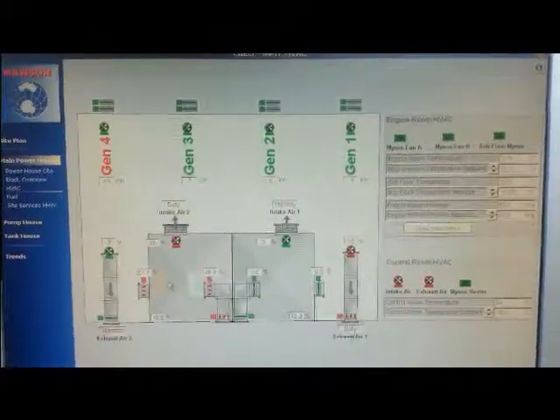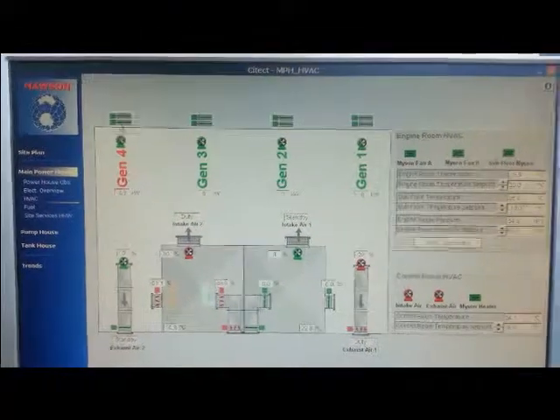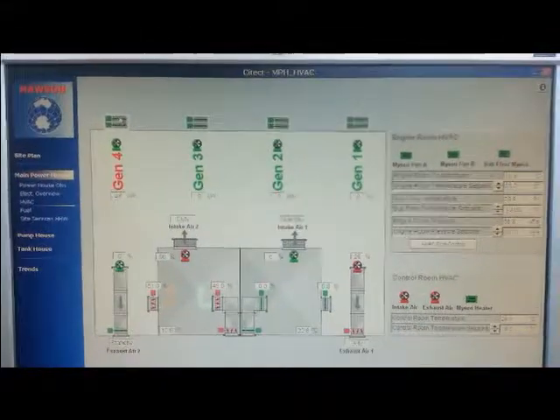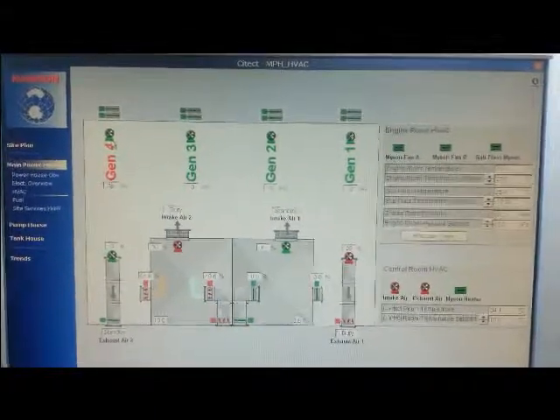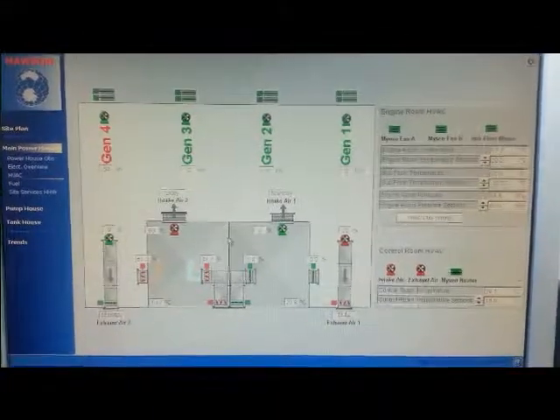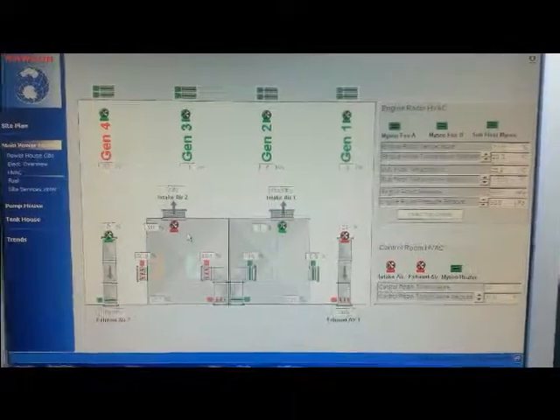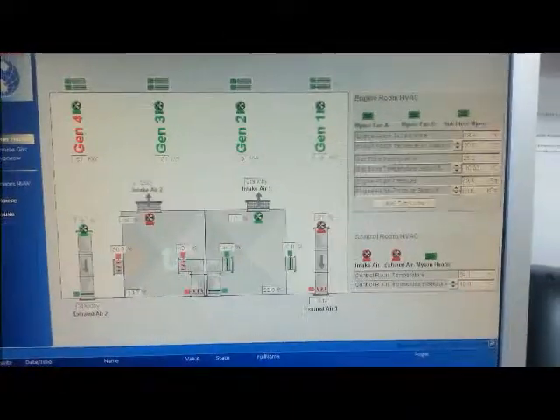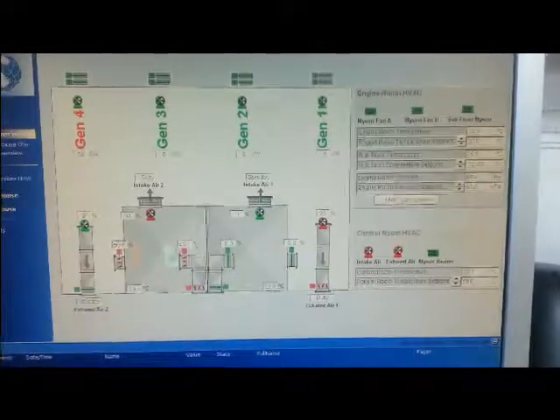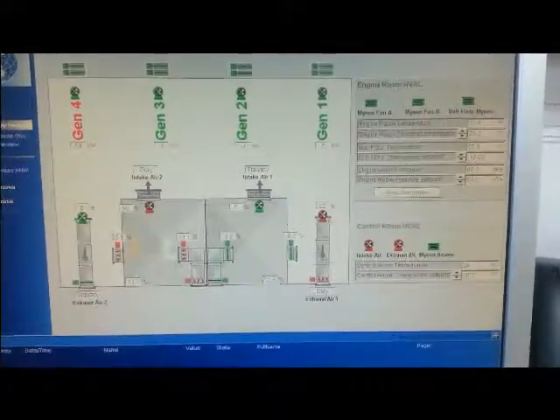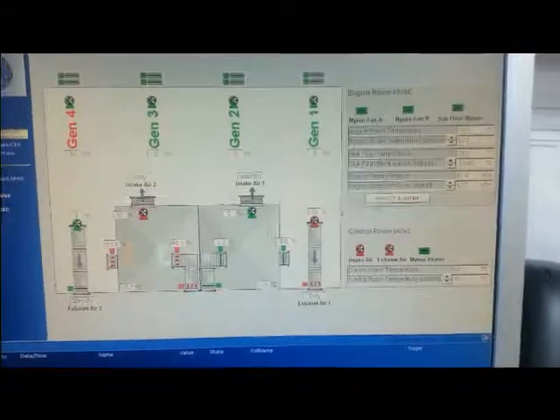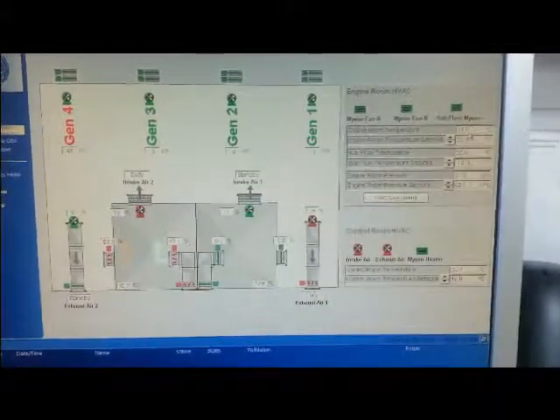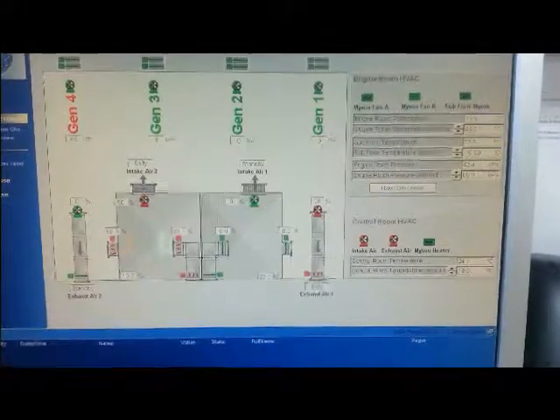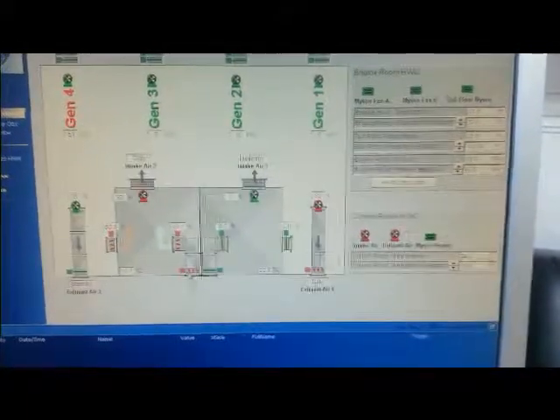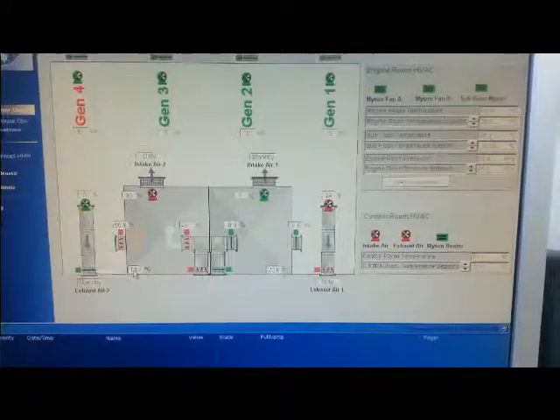Just an overview of the engine room here, showing the air handlers, as well as the gensets and the cooling radiators, the louvers and the cooling fans which open to cool them based on the engine water temperature. The room is pressurised here, done by a difference in the incoming air versus the outgoing air. It's also temperature controlled, so it's a bit of a juggle between this recirculating airflow versus the fresh air coming in. You see in the plenum we've got 10 degrees.